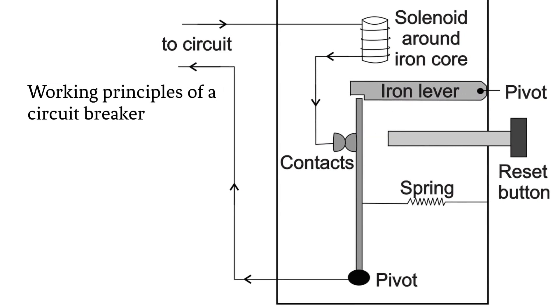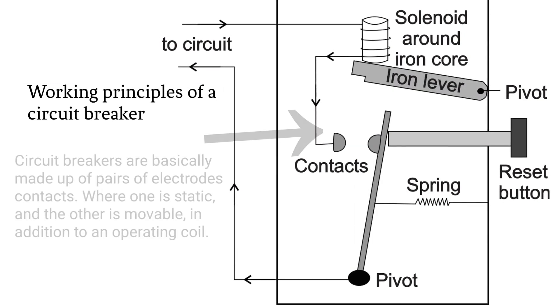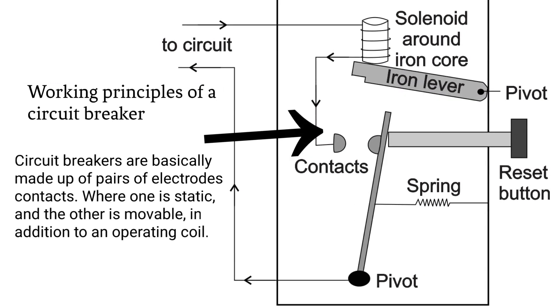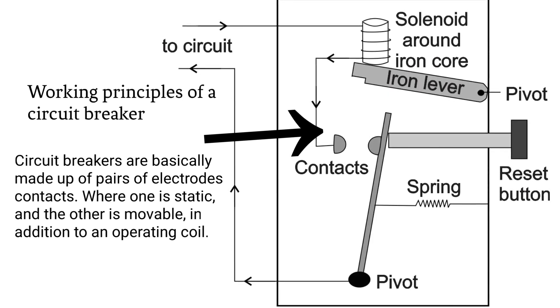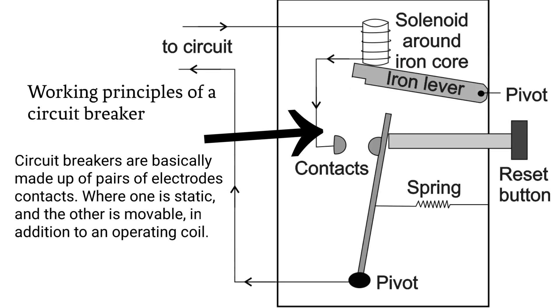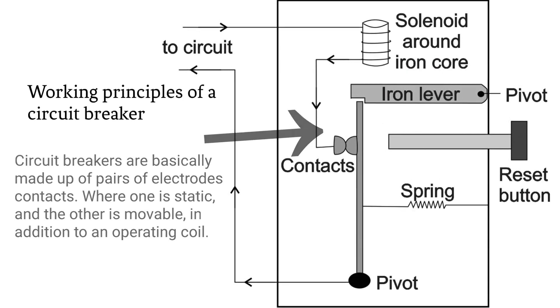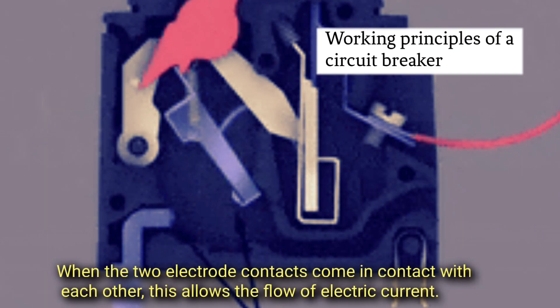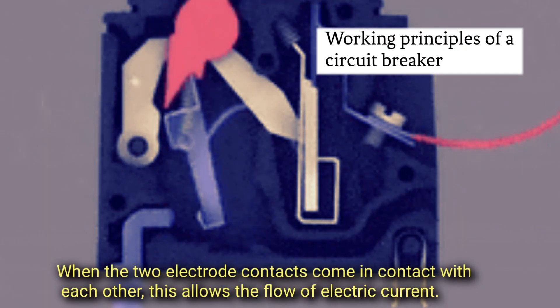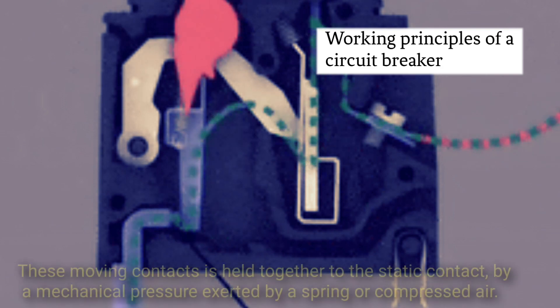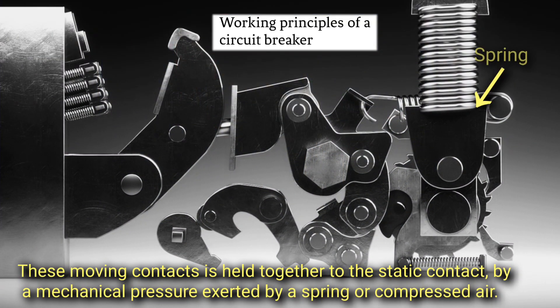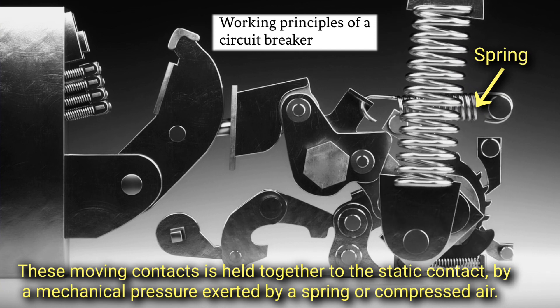Working principle of the circuit breaker. Circuit breakers are basically made up of pairs of electrode contacts, where one is static and the other is movable, in addition to an operating coil. When the two electrode contacts come in contact with each other, this allows the flow of electric current. This moving contact is held together to the static contact by a mechanical pressure exerted by a spring or compressed air.